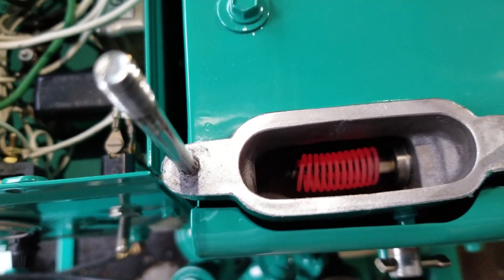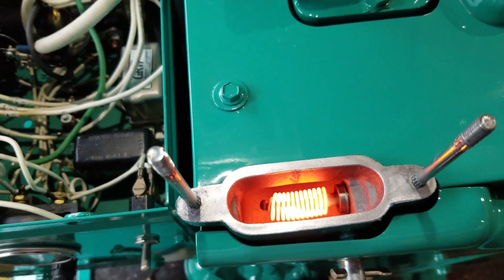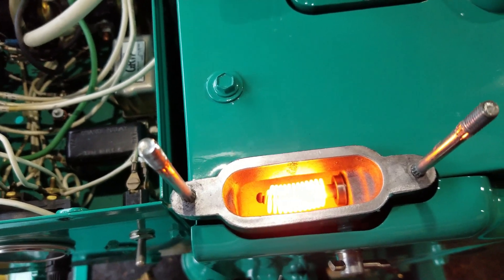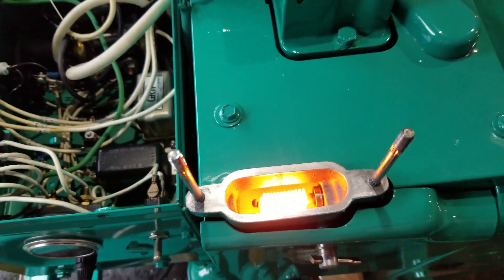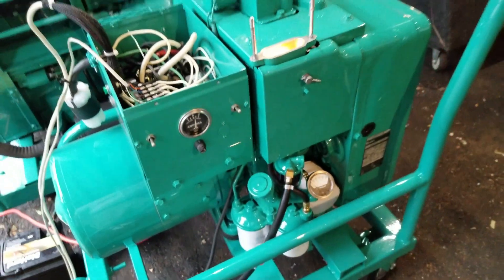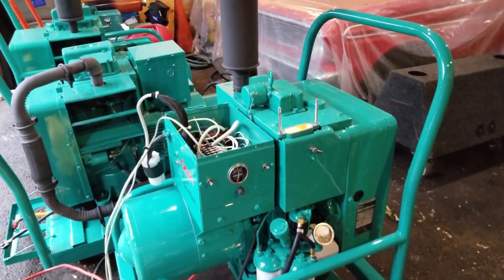Let me kill the breaker through the MIG welder outlet down below. The preheat should be on. Let's check the glow plug — there we go, turning cherry red. Now I don't know how many seconds I got this thing set for, maybe like 30 seconds or so. But usually these sets require about a good 30 seconds or so of preheat. I'm going to step back because once this thing starts kicking, it's going to get a little loud.